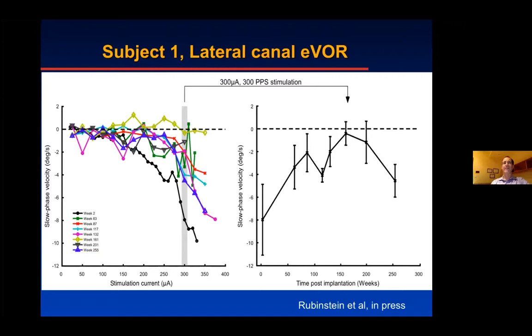Based on the results in those subjects, we developed a new version of the device to try to prevent the loss of effectiveness over time that we saw. And so we decreased the number of electrodes from 3 to 2, and we doubled the surface area of those electrodes to decrease their impedance. In our first generation device, the impedances were extremely high, in most cases over 20 kiloohms. And the cochlear device has a very difficult time driving any reasonable current level into such a high impedance. So by doubling the surface area, we thought we would decrease the impedance, and that proved to be true.